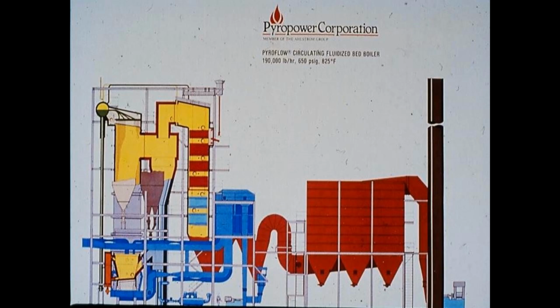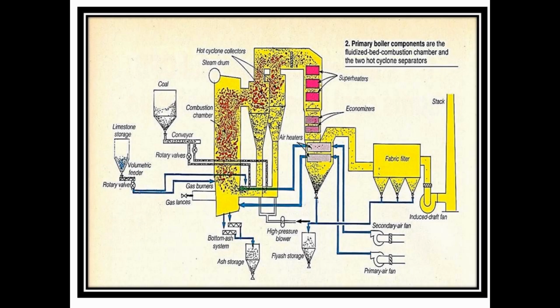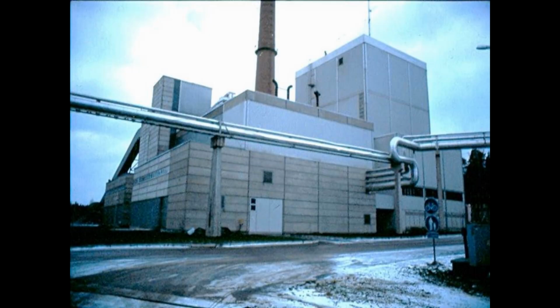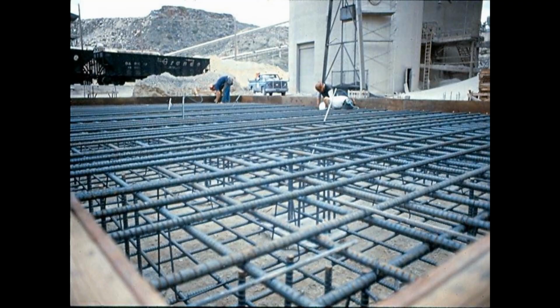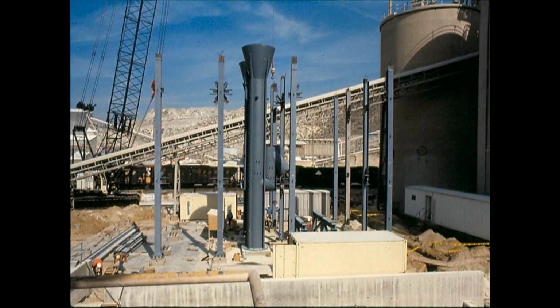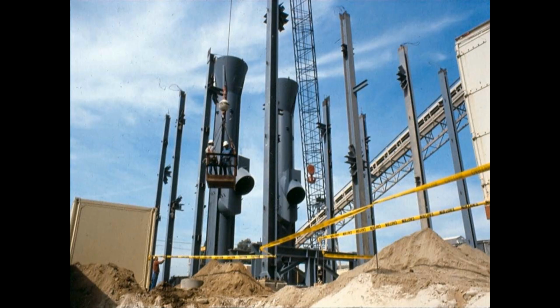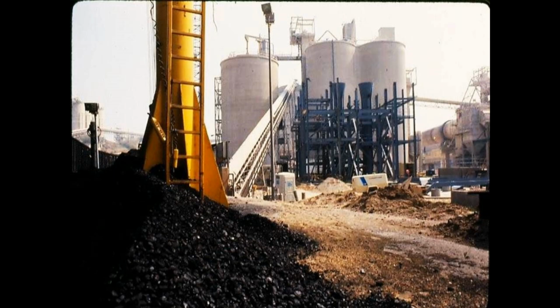Circulating fluidized bed boiler components comprise the combustion chamber, 2 hot cyclone separators, 2 superheater banks, an economizer, air heater, and fabric filter. The cement kilns use coal for fuel, and the existing coal handling and coal storage is adequate to handle the new circulating fluidized bed coal needs.